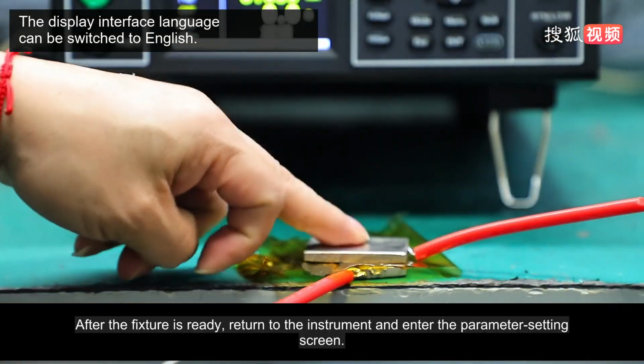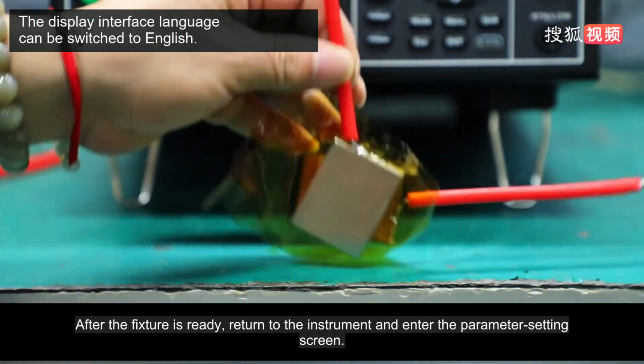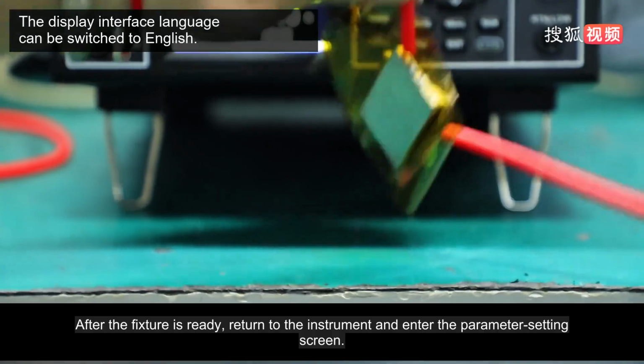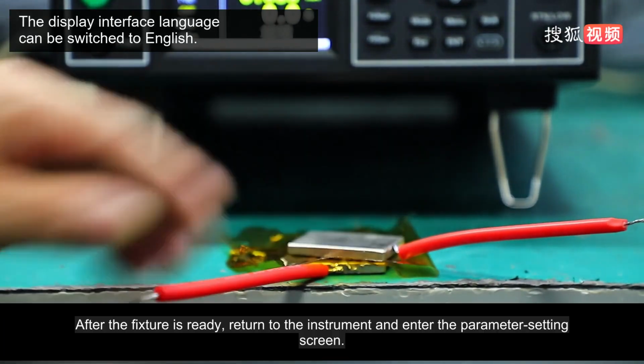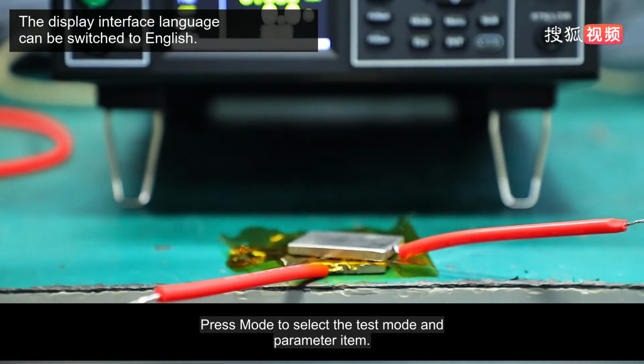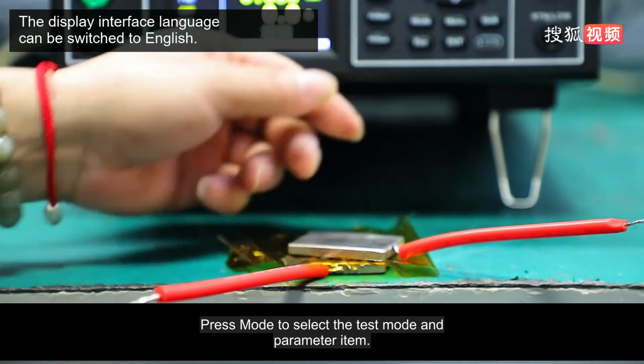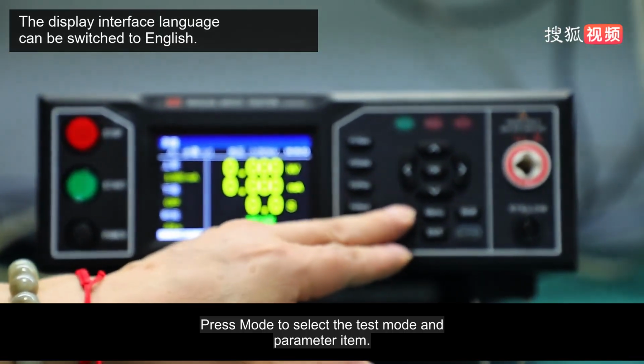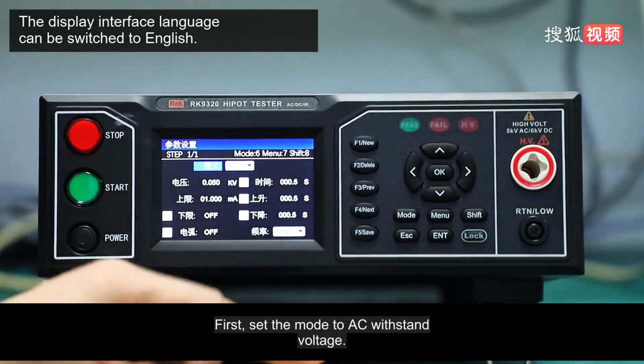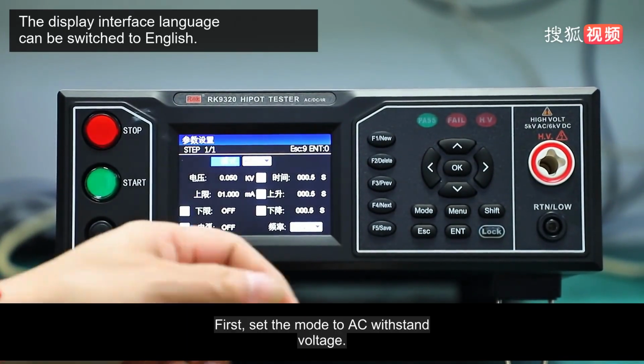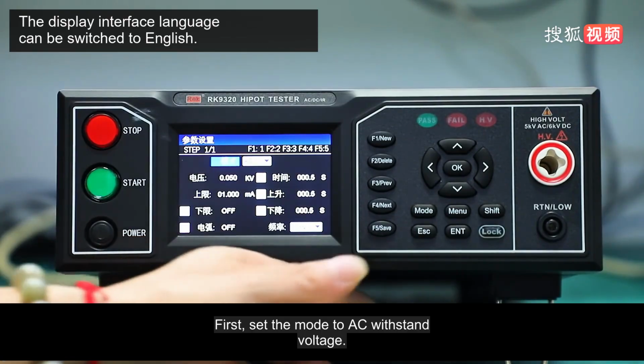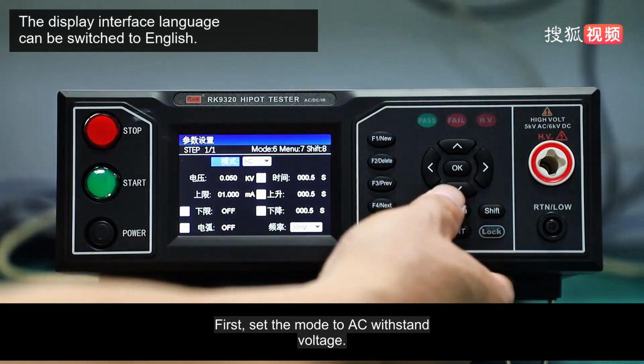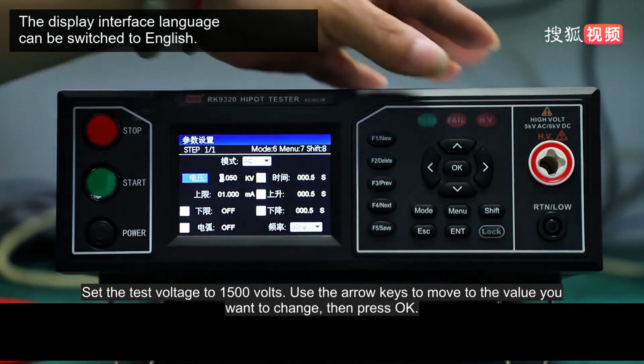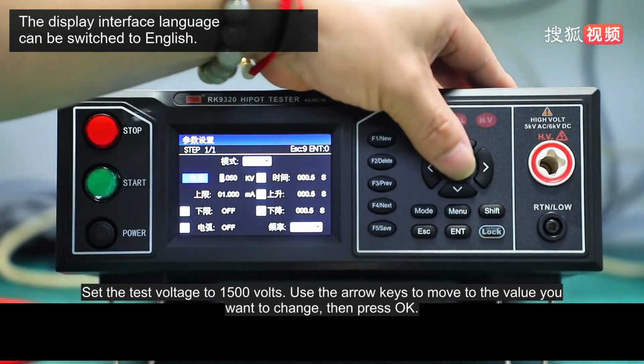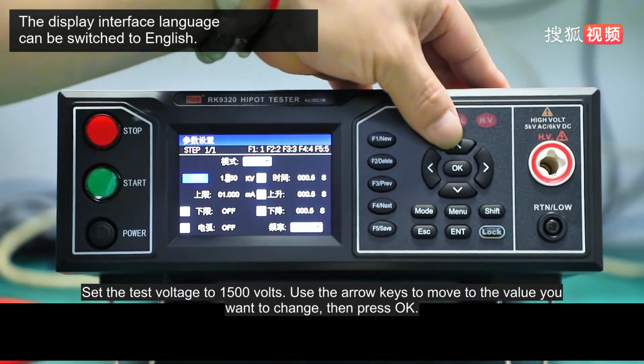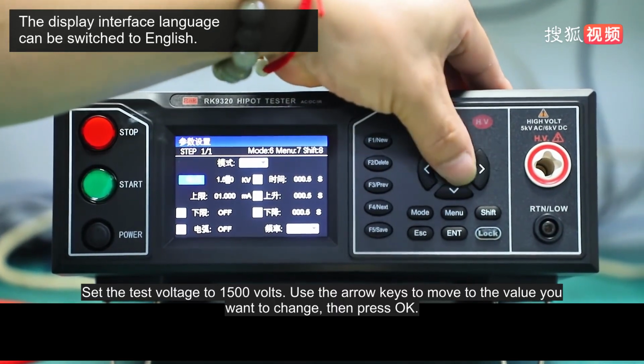After the fixture is ready, return to the instrument and enter the parameter setting screen. Press Mode to select the test mode and parameter item. First, set the mode to AC withstand voltage. Set the test voltage to 1,500 volts. Use the arrow keys to move to the value you want to change, then press OK.